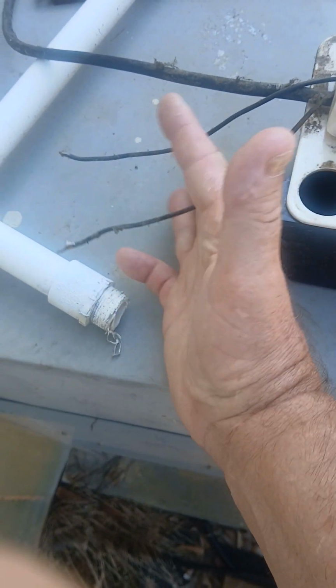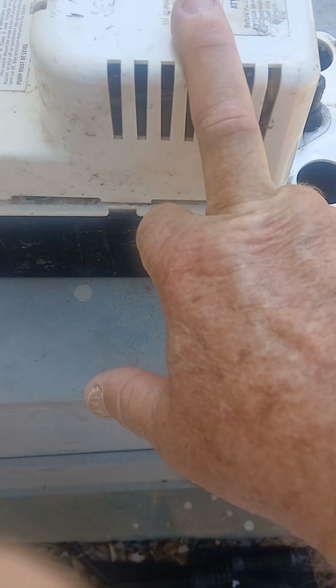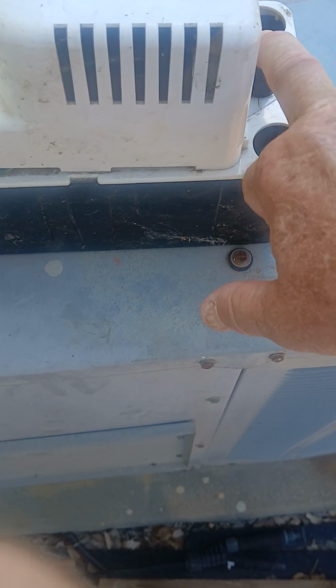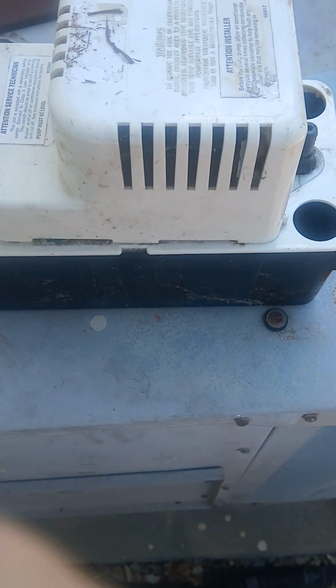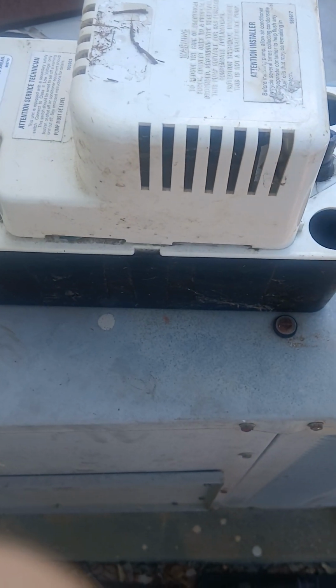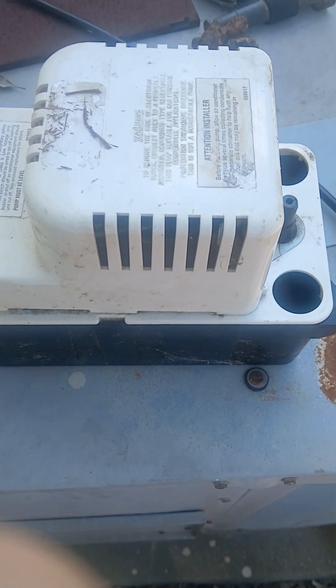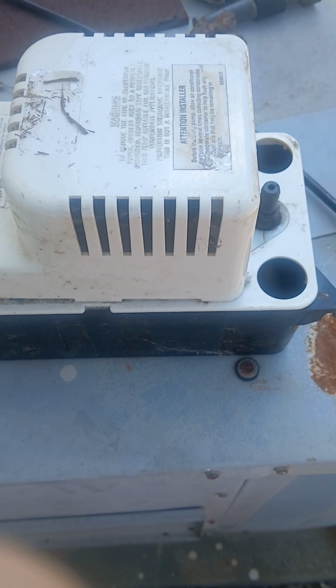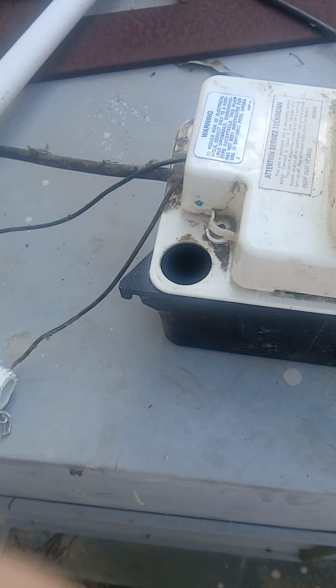But this may be just a safety, this wire here on your low voltage side to do the safety. So if the HVAC gurus could add this to the comments. And so I think you split the red wire here. Perhaps you may be able to split the yellow wire feeding, as long as the yellow wire and the common would be going to the condenser. But then if the water came here and the pump refused to come on for some reason, or if this got blocked up here, then it would shut the whole HVAC system off and protect you from water overflowing and cresting over here and perhaps hitting the drywall, hitting the floor, wherever you do not want water. So the basics of low voltage wiring for an HVAC condensate pump. Thank you.